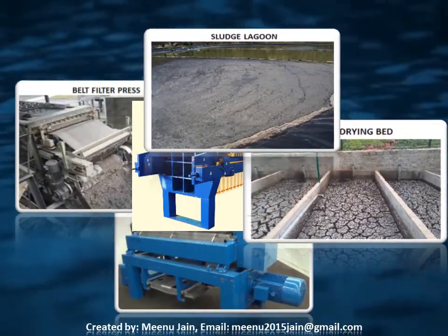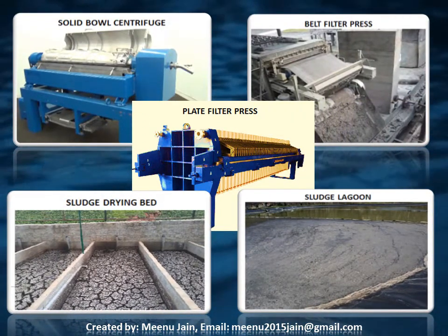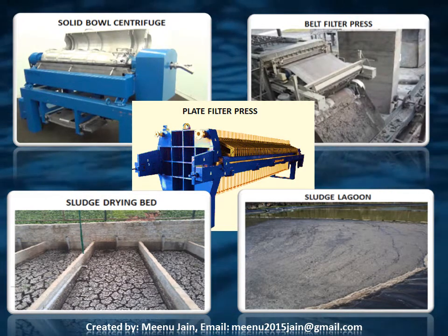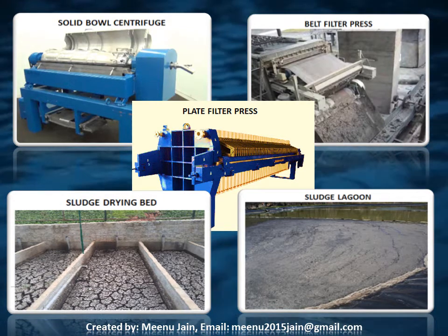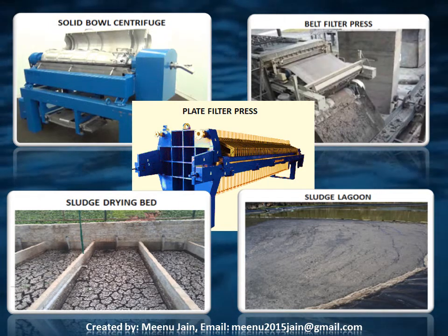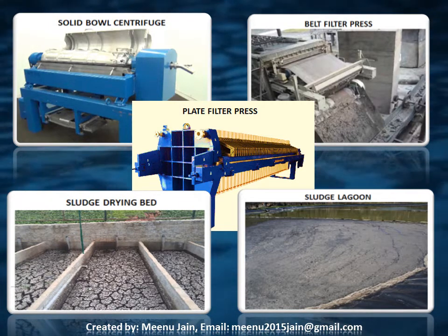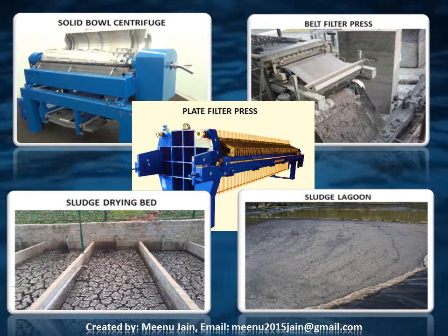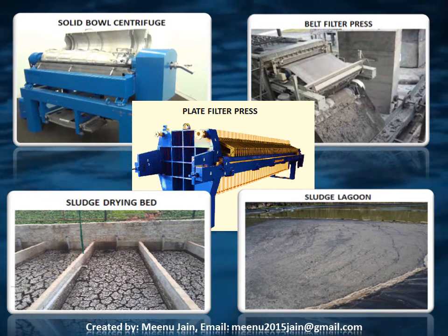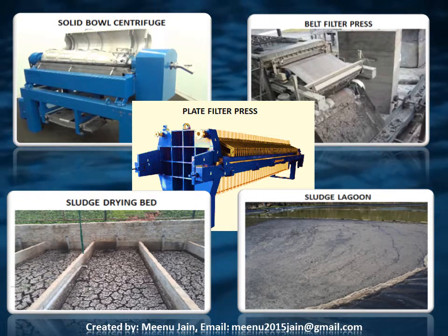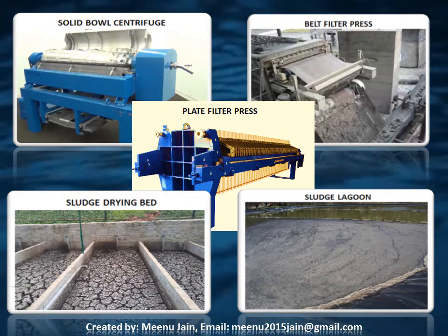Some dewatering equipment types include solid bowl centrifuge, belt filter press, plate and frame filter press, drying bed, and sludge lagoon. During industrial wastewater treatment, a huge quantity of sludge is produced. One treatment method is thickening the sludge using a solid bowl centrifuge. Prior sludge has a concentration of around 0.5–1% dry solids; after thickening, it comes up to 5–6% dry solids. This process reduces waste activated sludge volume by more than 80% and minimizes sludge amount for digestion by 30–40%.